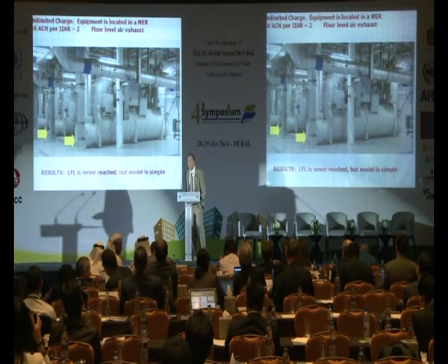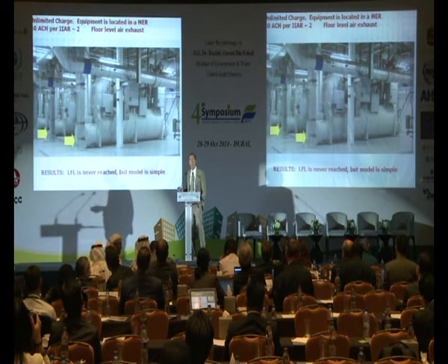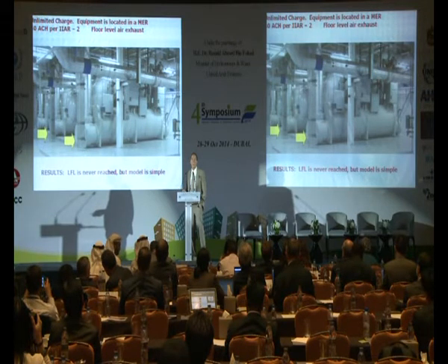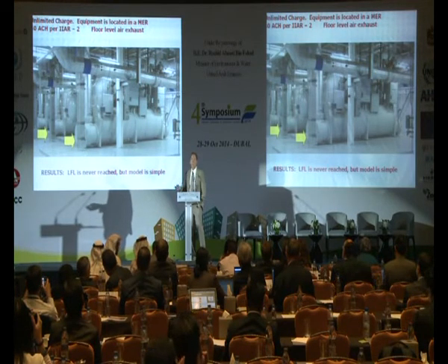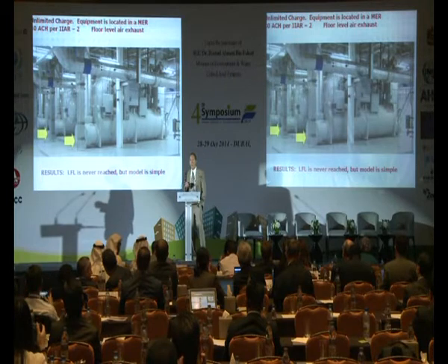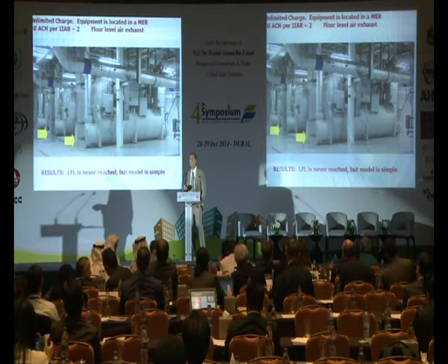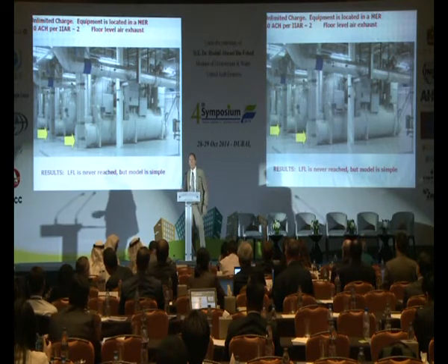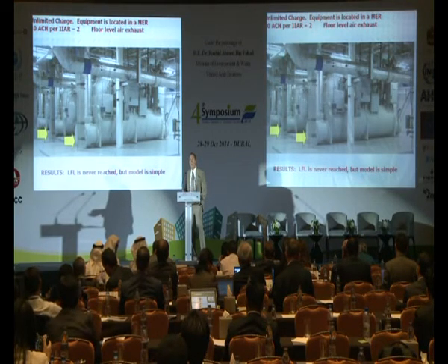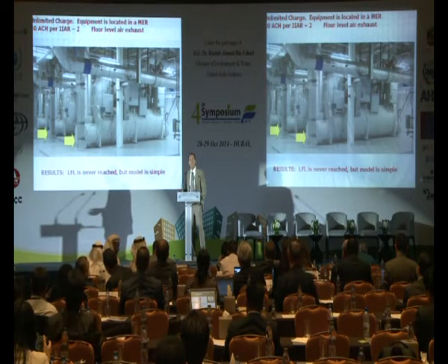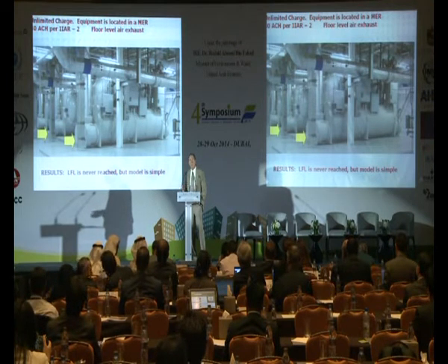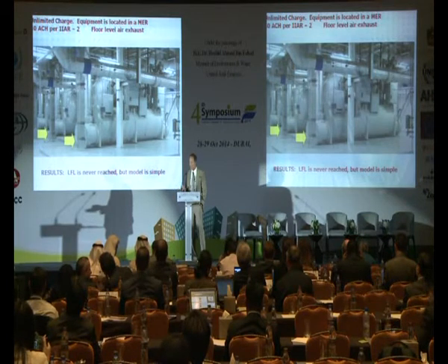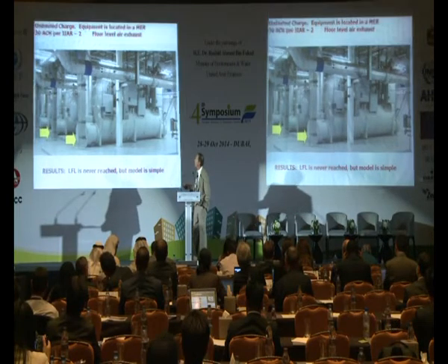I said I wasn't going to talk about equipment rooms, but I will mention it. Again, these are very, very large charge systems as opposed to charges that are limited by the RCL calculation. So in this case, we're talking about huge, huge chiller installations with unlimited charge. We did take a look at some of those cases, and basically, you just have to pump a lot of ventilation air and put the exhaust down on the floor, and once again, you have a relatively safe installation, but I'm not going to go into that in the interest of time.